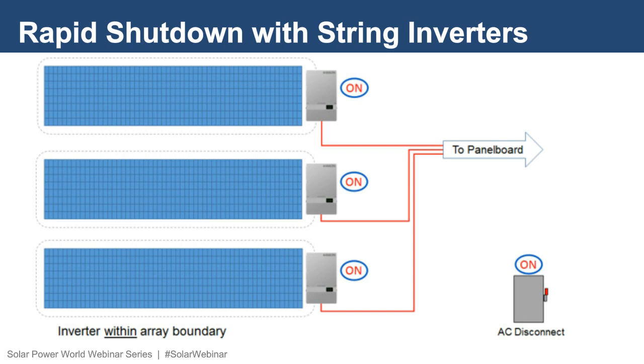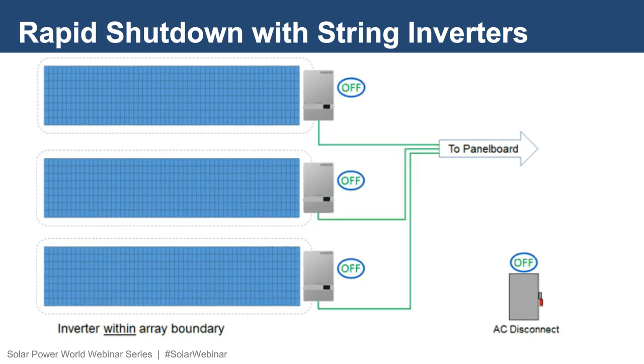When the AC disconnect switch is closed, these conductors are energized. When rapid shutdown is initiated, the switch is opened, the AC conductors go dead, and the inverters stop energizing due to the requirements of anti-islanding. So long as you can install the inverter within the array boundary, this may be the most cost-effective solution for you to meet the array level rapid shutdown and not require any additional equipment beyond the use of transformerless string inverters.